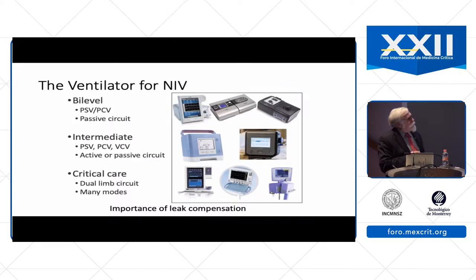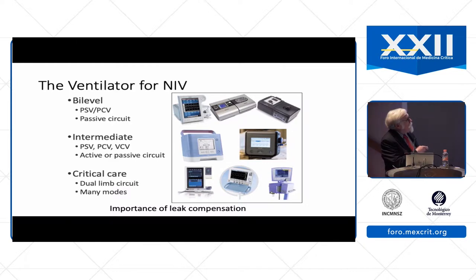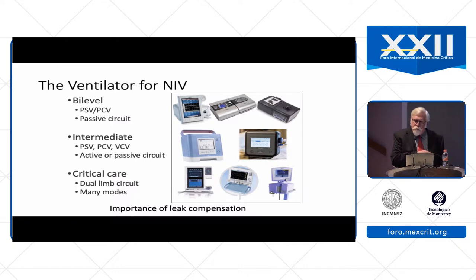There are a number of ventilators that can be used for non-invasive ventilation. I typically group those into bi-level devices, intermediate devices, and critical care devices. The bi-level devices use a passive circuit. The intermediate devices can use either an active or a passive circuit. The critical care devices use a dual limb circuit, and many of the current generation critical care ventilators have non-invasive ventilation modes.